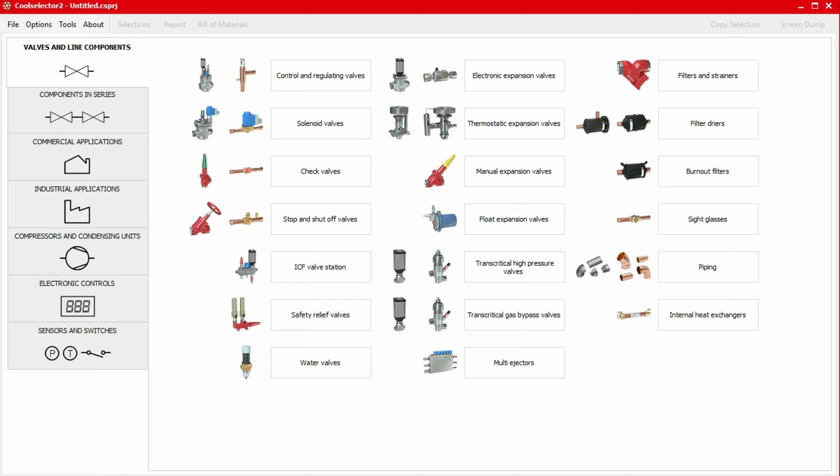For example, an ICM valve can be used as an expansion valve, a control valve, or a slow opening solenoid valve. However, each of these functionalities results in a different consideration for the selection and calculation. We should always use the proper functionality to choose the valve so that we get the relevant required information to make a good decision.